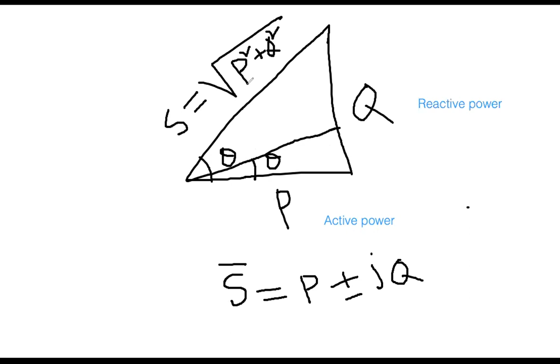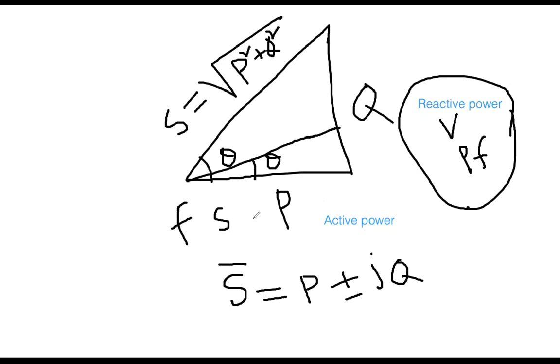That is fine, but still reactive power, voltage, and power factor are the dominating factors in case of the induction machine. So if it's an induction machine, you have to give priority to controlling these three factors. If you don't, for example if it's an induction machine but you give priority to controlling active power, frequency, and speed, the system might come back to a stable condition, but there might still be some oscillation. Similarly, if your system is a synchronous machine, your preference or dominating mode should be controlling frequency, speed, and active power. But if you start controlling the other things, the system might come back to stable position because of this interrelationship, but it might not be appropriate.